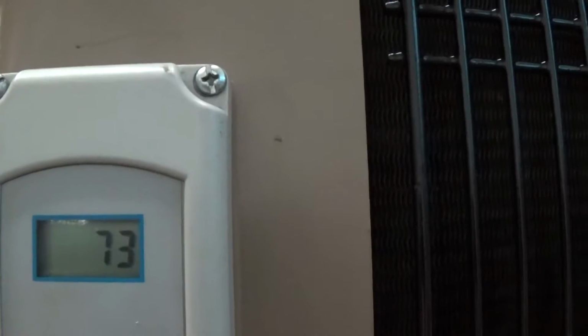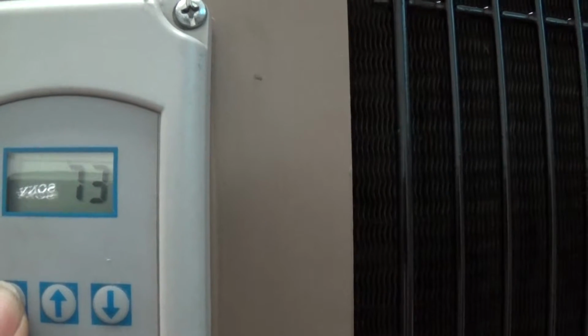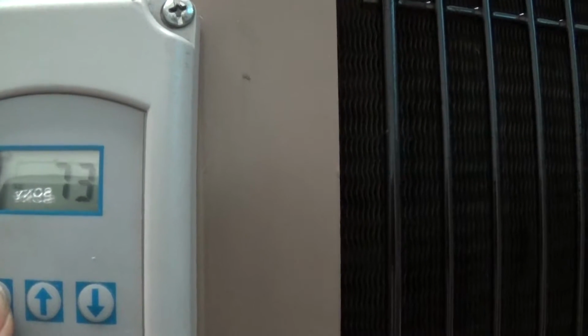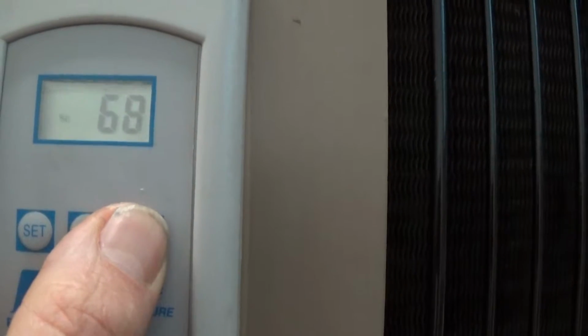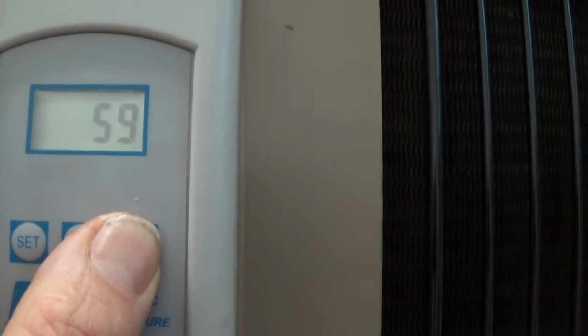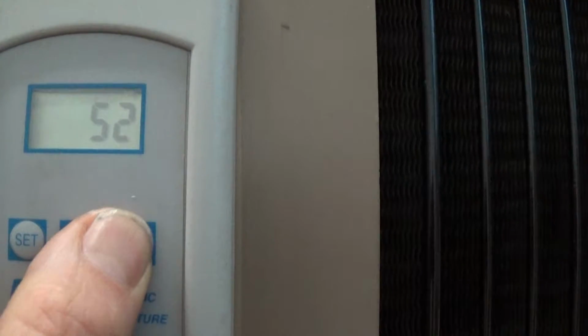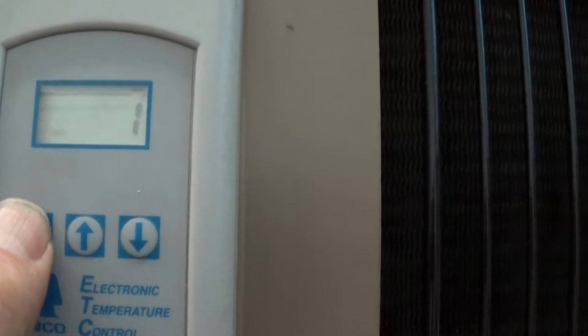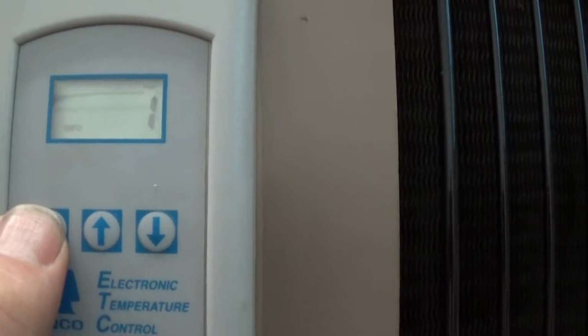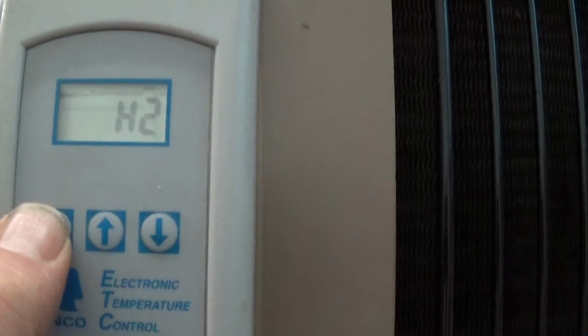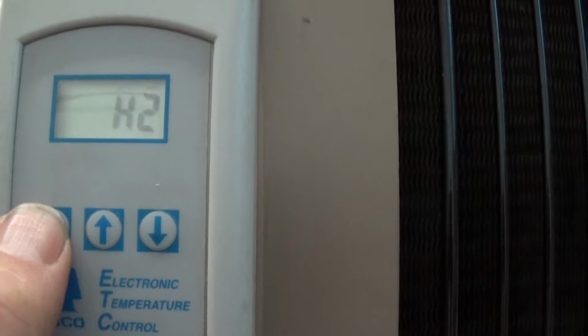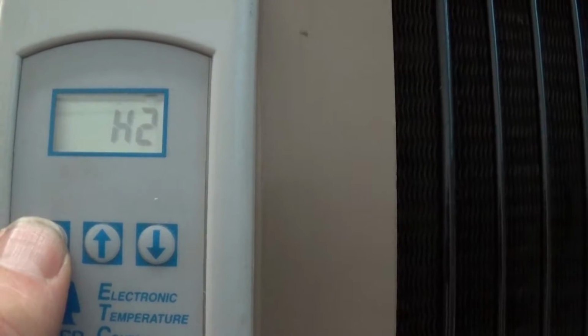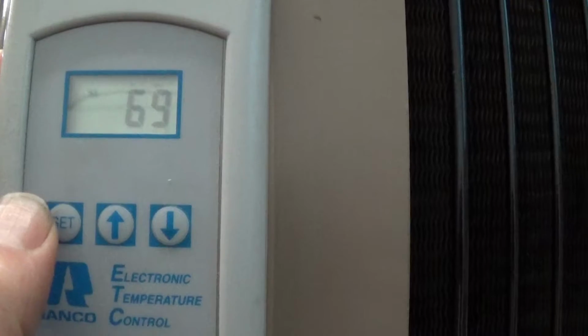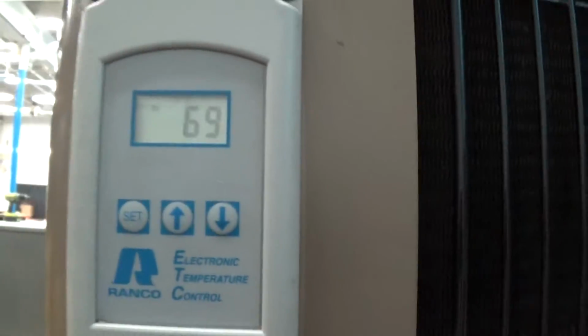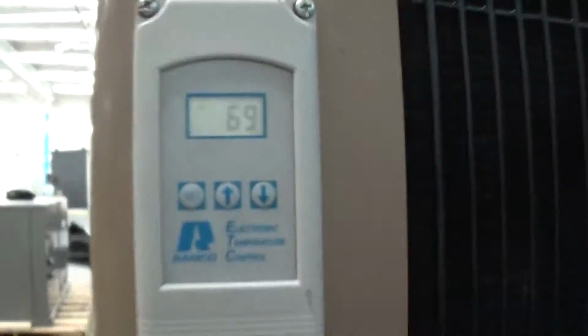Now we're going to go to set point 2 at 73. We want set point 2 to be, let's say, about 2 degrees higher than set point 1. So we're going to bring that down to 50. That's your hot gas bypass. We press set again. We're going to leave the hot gas bypass a differential of 1. Set again, leave it at H2. The way this is set up, leave the hot gas bypass at the H2 option. Set again, and that returns back. So now we're on.